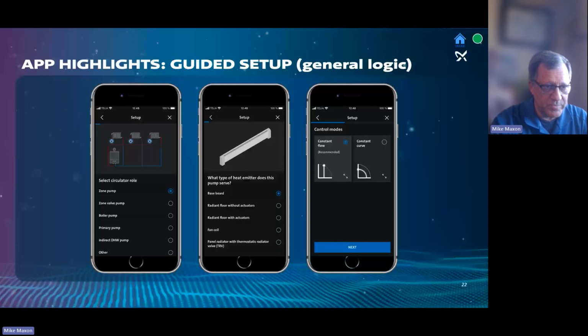This is a couple examples. The first screen is going to ask you, what type of system is this? And it'll give you a drawing of that system, so we make sure we're talking about the same pump. If it's a zone pump, it shows you what the zone pump is. So make sure that, again, we're talking about the same thing. Then the next screen is going to ask, okay, on this zone pump, what kind of heating elements are you using? In this case, baseboard. The next screen is going to say, okay, the mode that we recommend for this would be a constant flow. You could also do a constant curve, but we recommend constant flow.